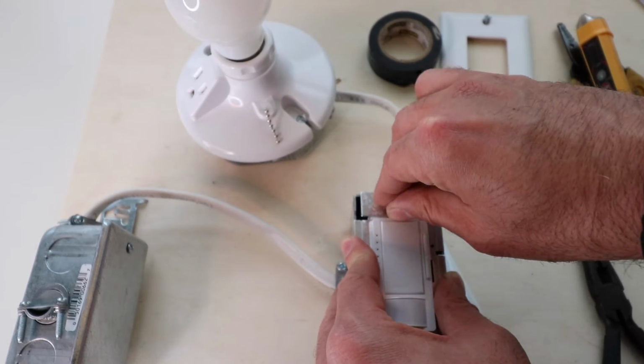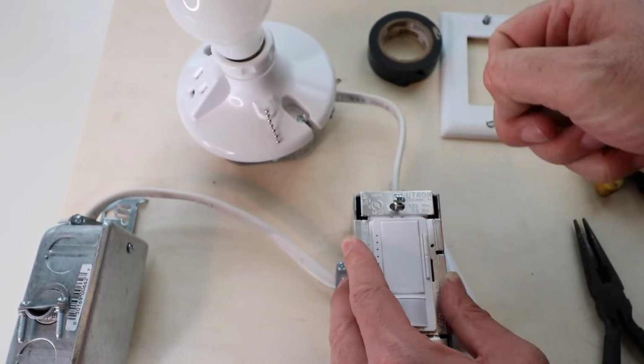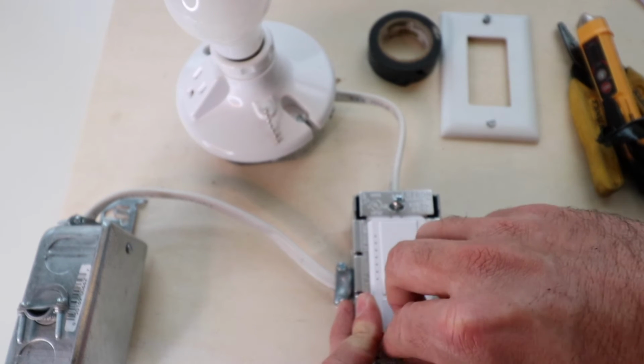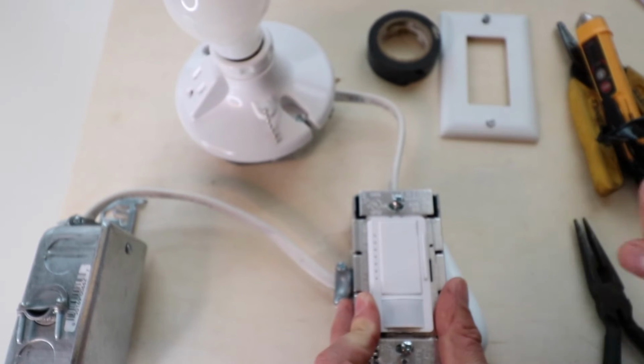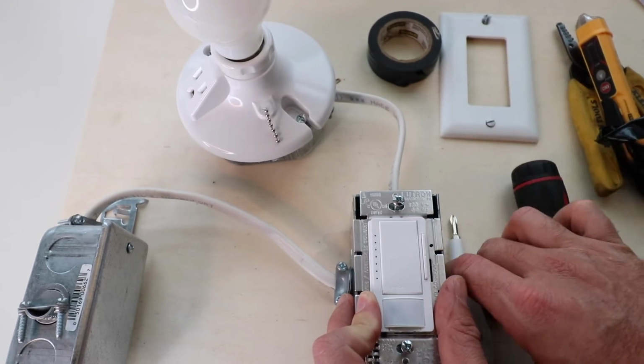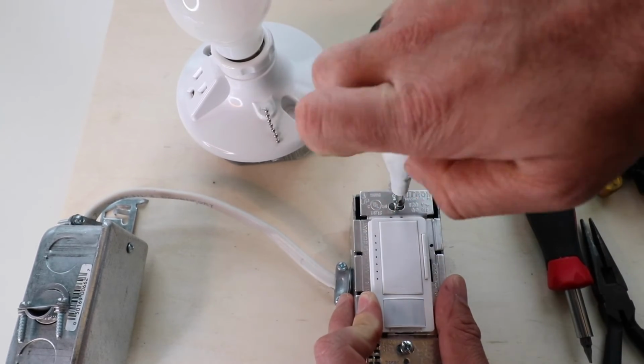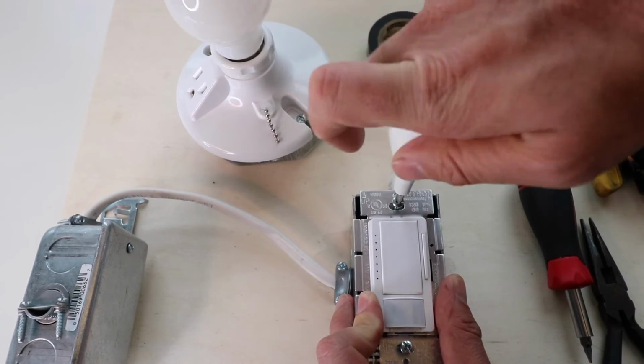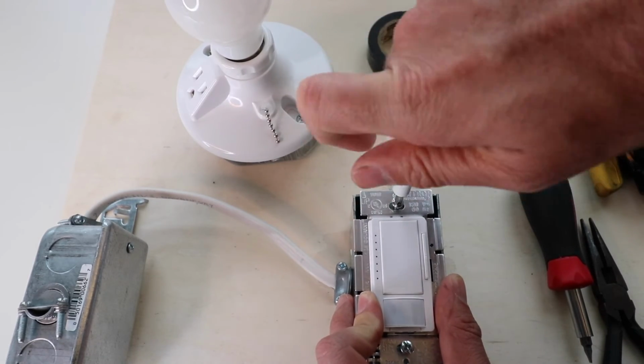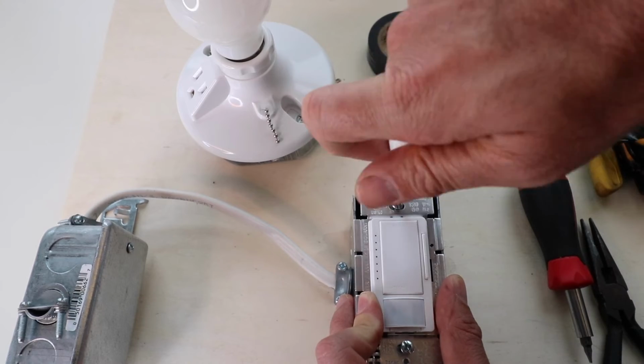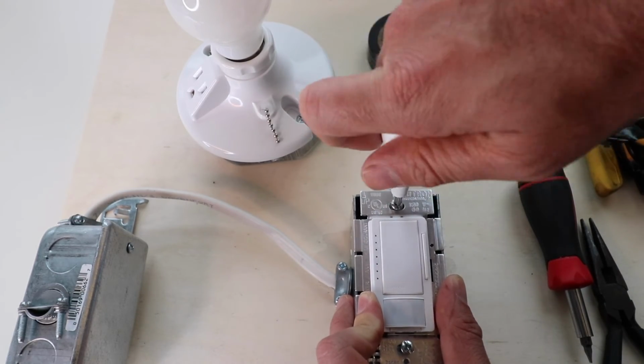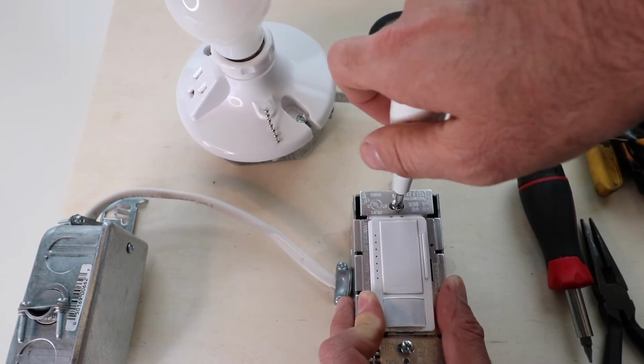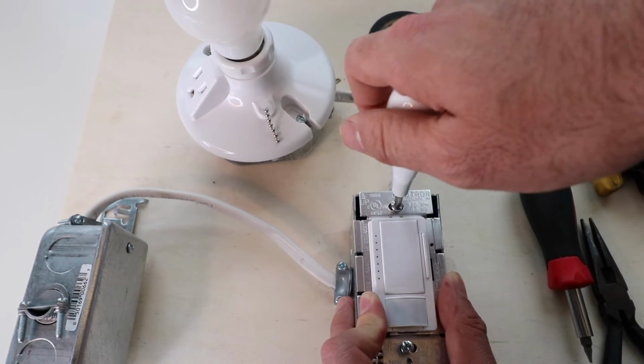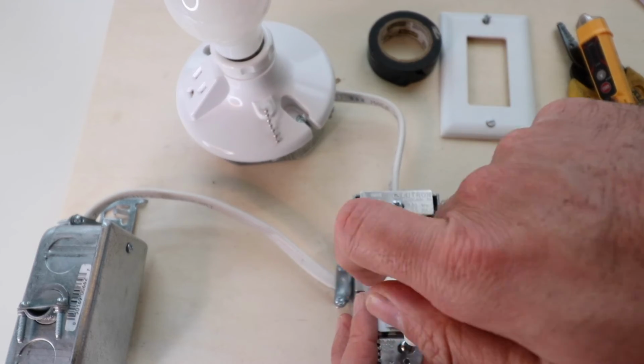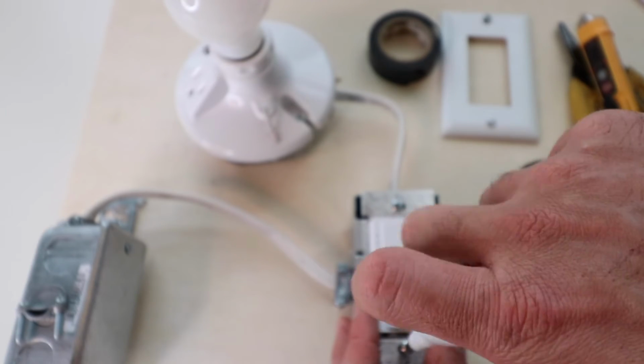Now what we're going to do is put our two screws that hold the light switch into the junction box in here. Go ahead, screw those in, and get them tightened down, both top and bottom. I like to get them moderately tight and then adjust a little bit, since sometimes you need to adjust if you've got other switches in the same junction box, or just to get the light switch correctly level and vertical and looking good.